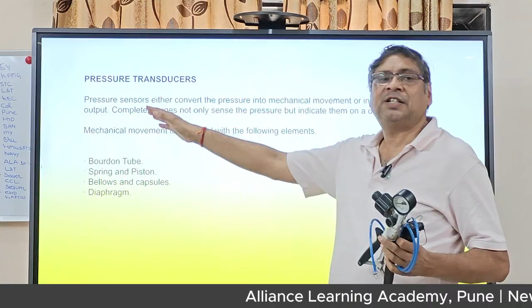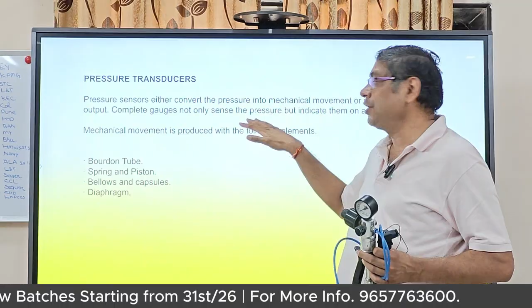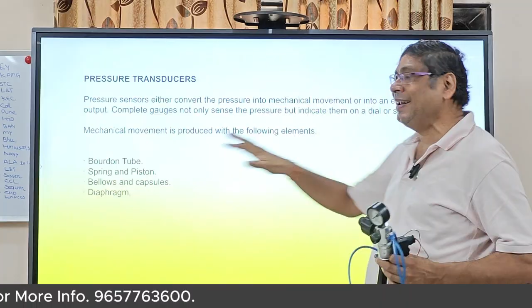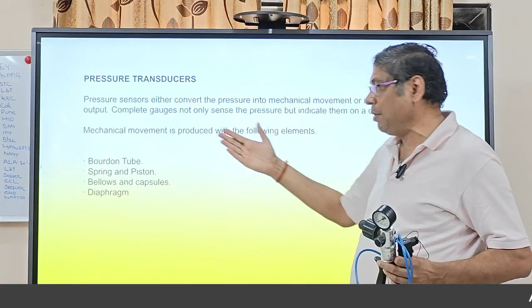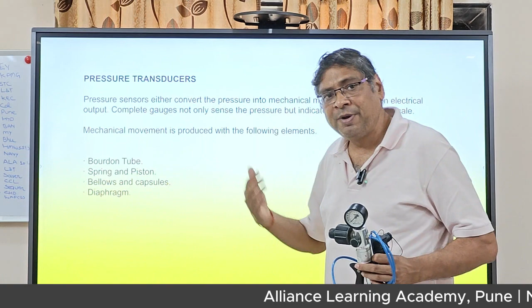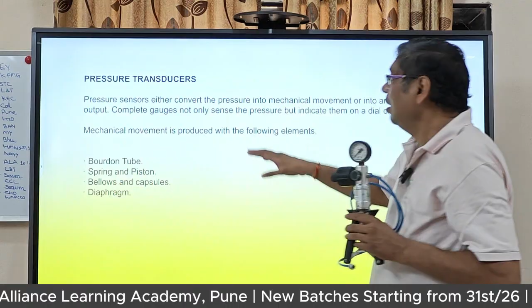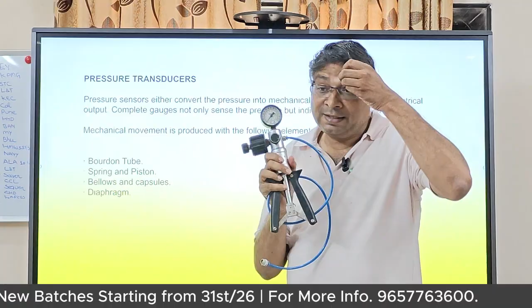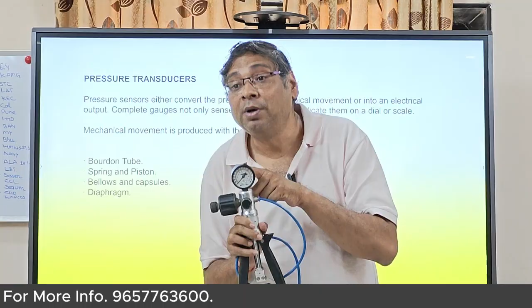So now what are we talking about? Pressure sensors either convert the pressure into mechanical movement or an electrical output. Complete gauges not only sense the pressure but indicate it on a dial or scale. Mechanical movement is produced with the following elements: it may be a Bourdon tube, a spring piston, bellows, a capsule, or a diaphragm. Now analyze the first words: convert the pressure into mechanical movement. If you see this, this is the pressure gauge. Inside that, what is there? A Bourdon tube.